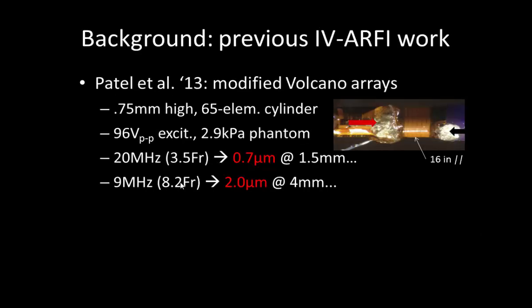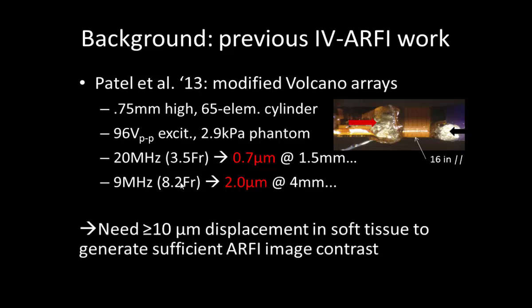Our group previously attempted to generate ARFI displacements using a modified array that's commercially available from Volcano. To do this we connected 16 elements from the 65-element cylindrical array in parallel and drove them in unison in contact with a gel phantom. Unfortunately, the displacements that were achieved were much too small for ARFI imaging. So one of the primary challenges is simply to achieve a greater radiation force and displacement from an intravascular device to achieve sufficient ARFI contrast for imaging.